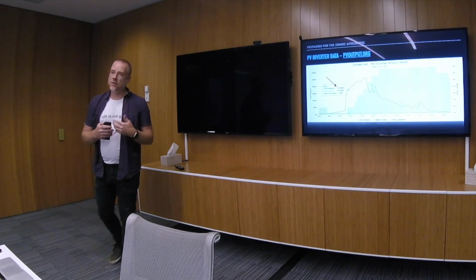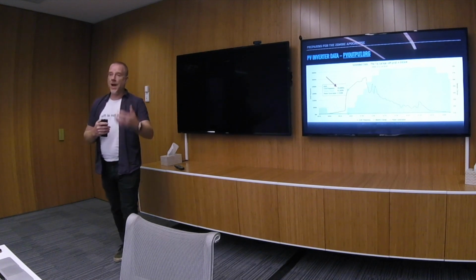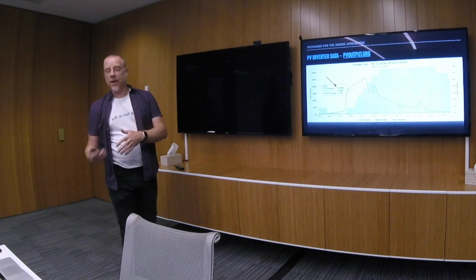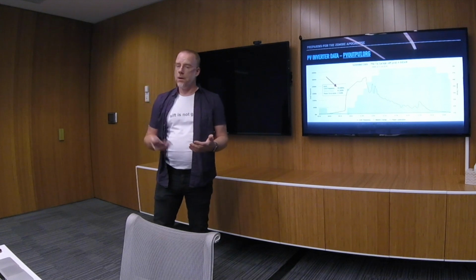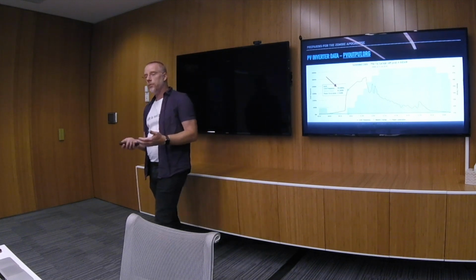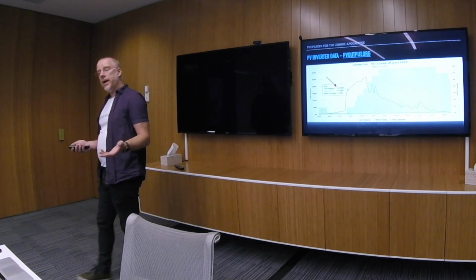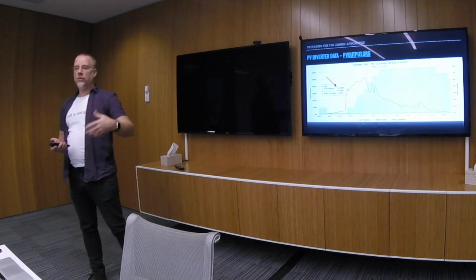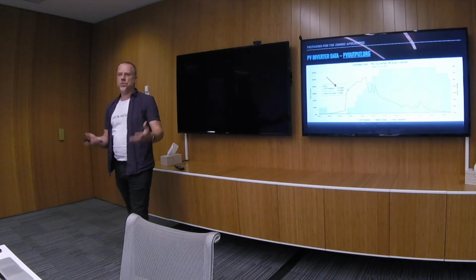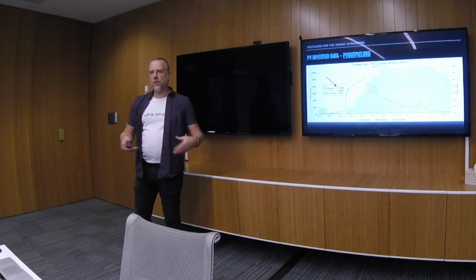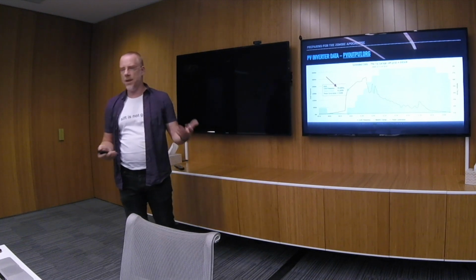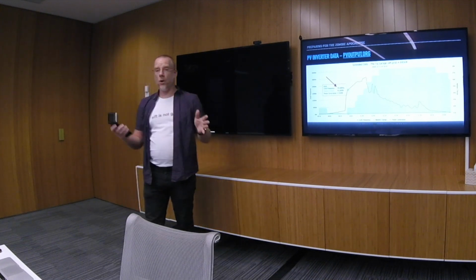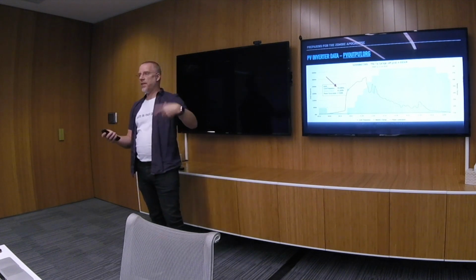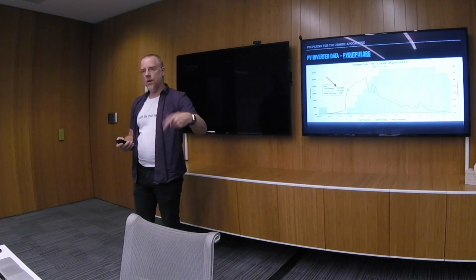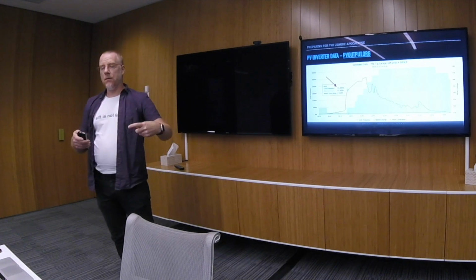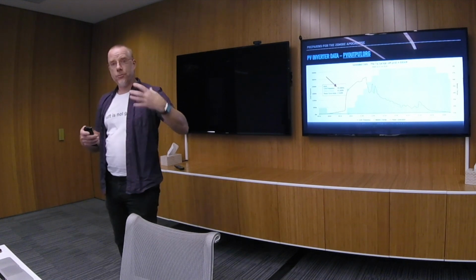When there are times of demand, so when demand exceeds supply, the frequency of the grid drops a little bit. Think about the load you're imposing on a generator, like a diesel generator. If it's spinning at 1,000 RPM with no load, it produces 50 hertz. Once you start putting a load on it, the generator has to respond.